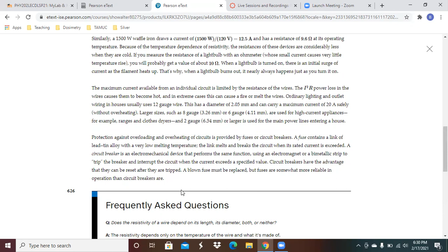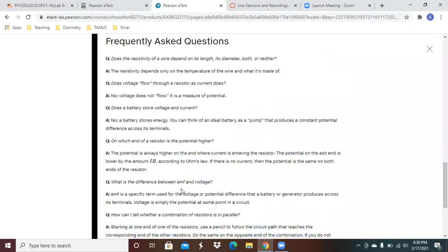Protection against overloading and overheating of circuits is provided by fuses or circuit breakers. So a fuse is going to contain a link of lead-tin alloy with a very low melting temperature. The link melts and breaks the circuit when the current rating is exceeded, which is what you're looking to do because you don't want it overloaded. The circuit breaker is an electromechanical device that performs the same function using an electromagnet or bimetallic strip to trip the breaker and interrupt the circuit when the current exceeds a specific value. Circuit breakers have the advantage that they can be reset. A blown fuse must be replaced, but fuses are somewhat more reliable in operation than circuit breakers can be.